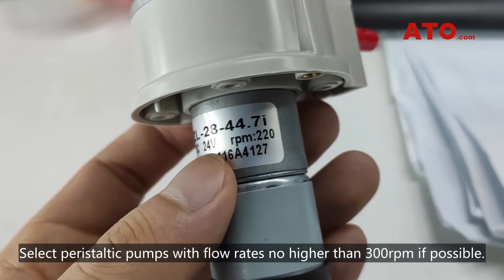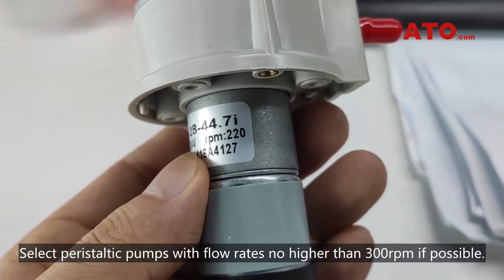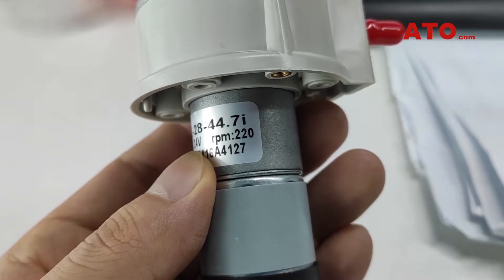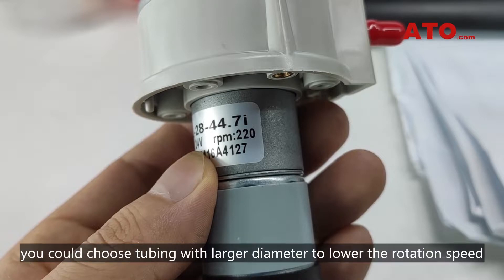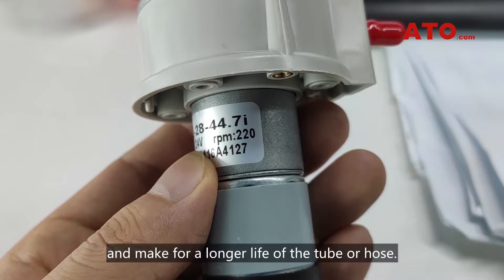Select peristaltic pumps with flow rates no higher than 300 rpm if possible. As the peristaltic pump generates flow rates from rotating rollers, you could choose tubing with a larger diameter to lower the rotation speed and make for a longer life of the tube or hose.